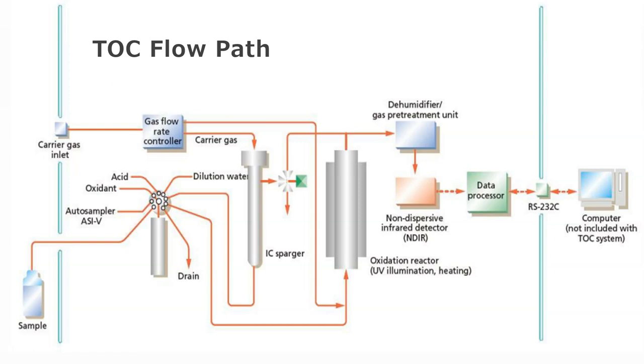Here we see a diagram of the flow path for the instrument. Our two main inlets are carrier gas, which is typically some ultra pure air or another inert gas, and our sample, which is injected using an auto sampler. This eight-port diverter valve is a very important part of the instrument since it connects all of the influent lines and controls where the flow is going. It connects the sample, the auto sampler, the oxidant, acid for sample acidification, dilution water, and our combustion chamber or oxidation reactor as it's sometimes called.